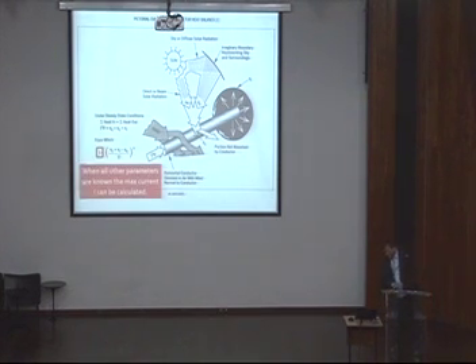Now, that's already the problem. What you typically know during operation is the current of a line, but are all the other parameters known? It's the wind speed, the wind direction, the solar. You might have an idea about emissivity and absorptivity. What you also know is the cross-section, which has an impact. So some of the parameters you know, but most of them you don't know from the line. So what conditions do you have in the line? Okay, this is what I said. When all the other parameters are known, the maximum current I can be calculated.